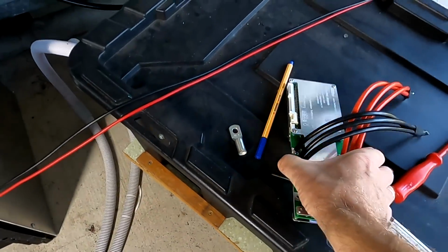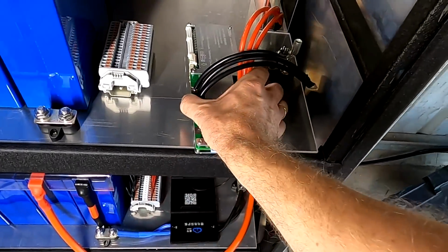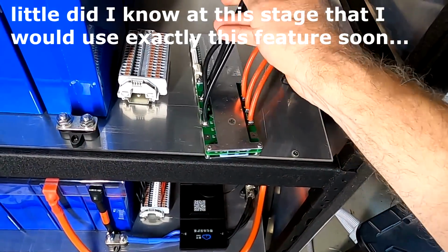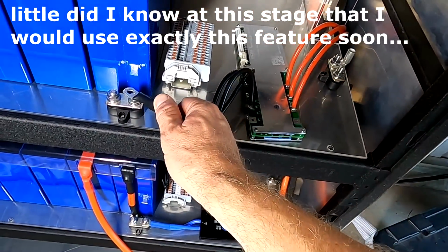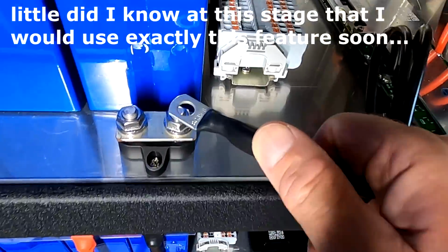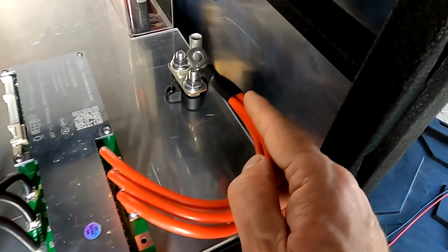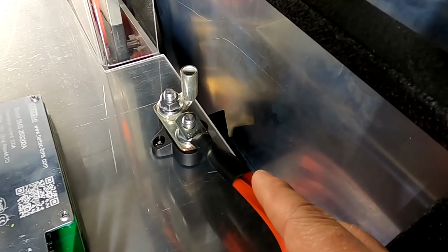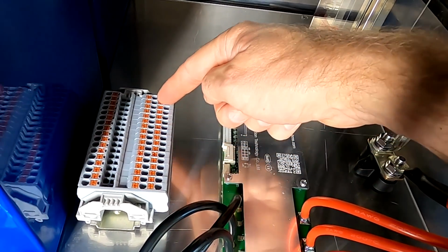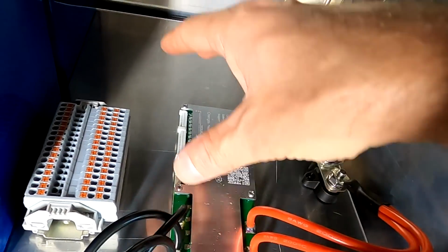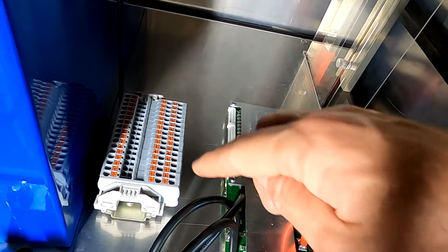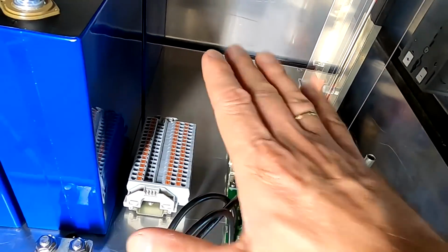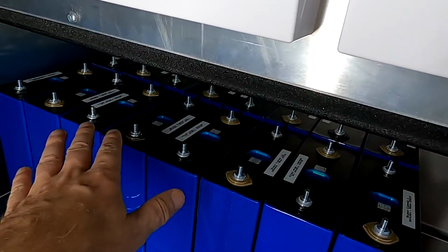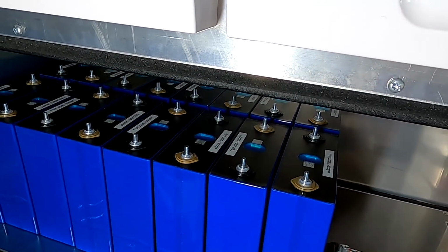This gives us the flexibility to quickly replace a BMS for one battery bank, because it's just connected to one of the little bus bars on this side as well as on the load side. Then we can disconnect all our balance leads, put another BMS or balancer in, and connect this back to the terminal block, and we are done. We don't need to touch any of the terminals of the batteries at all.